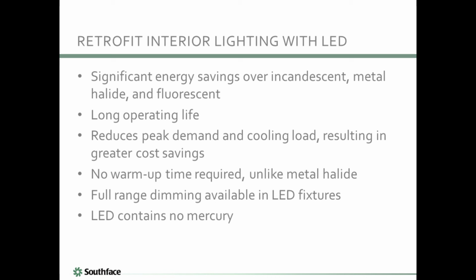Interior lighting energy consumption usually occurs coincident with peak demand. Lighting energy also reduces the cooling load for a building, which produces additional savings. Due to the reductions in both cooling and lighting energy and demand savings, interior lighting retrofits have a high cost savings. LED also provides the benefit that there's no warm-up time required, unlike metal halide. LED fixtures also provide great controllability, with full range dimming available.